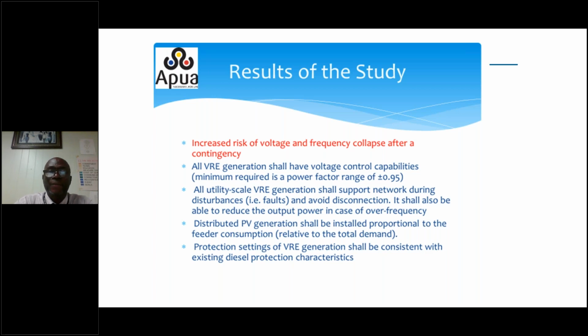So what are the results of the study that was done by IRENA? IRENA recognized various challenges with the grid in Antigua, and this is coming straight from the report. They indicated that there'll be increased risk of voltage and frequency collapse after contingency. Contingencies are if we lose a major line, if we lose a major generator. Now, we know that our system does not normally provide the same amount of VAR support as the traditional fossil fuel. So IRENA recommended that all VRE generation shall have voltage control capabilities. And that is something that we have insisted on: any new RE system that comes online must have that.